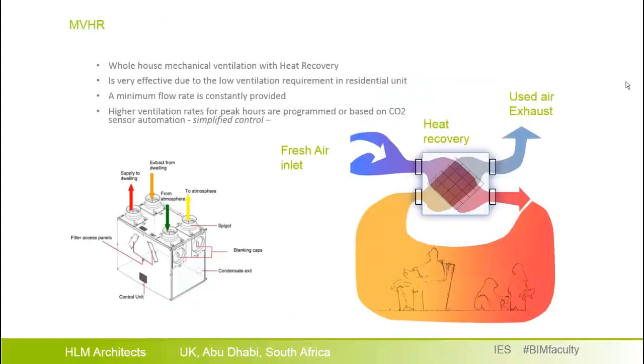The mechanical ventilation with heat recovery, bypassing the windows, provides higher rates of fresh air which is preconditioned by the heat recovery. Heat recovery works by extracting the heat accumulated in used air prior to exhausting it outdoors, and passing this heat to fresh air which is then supplied to the rooms.